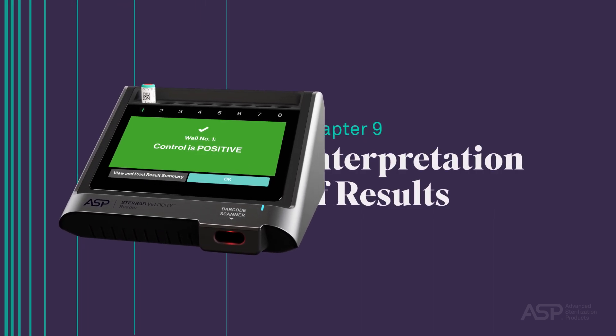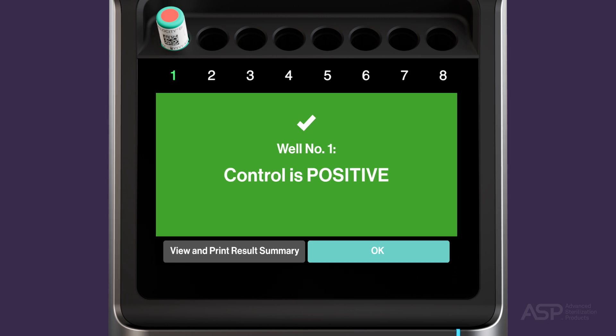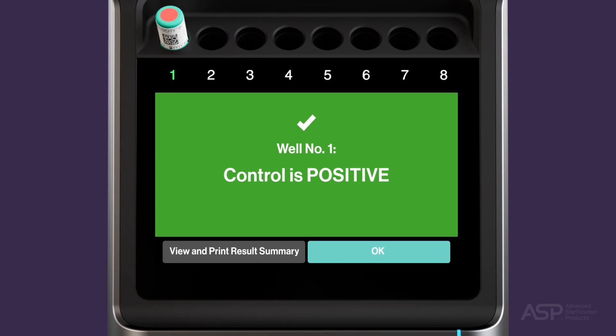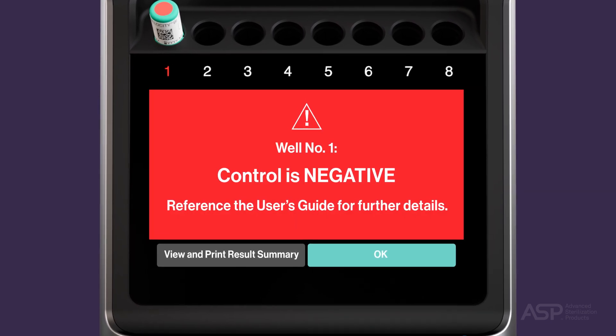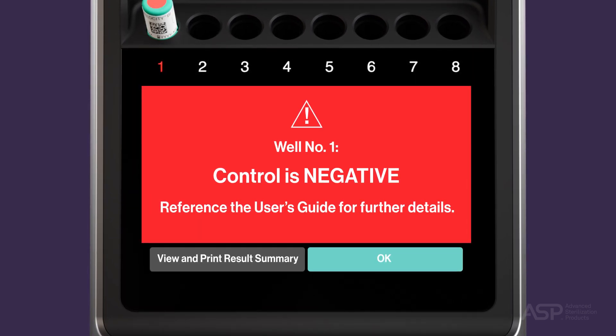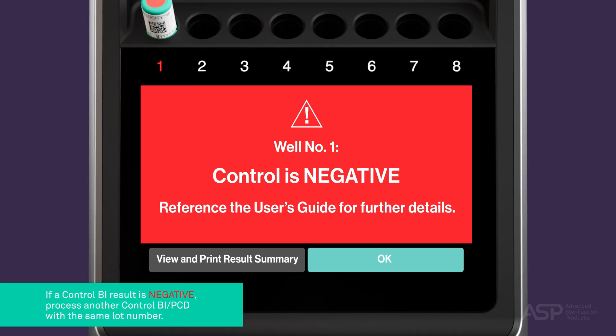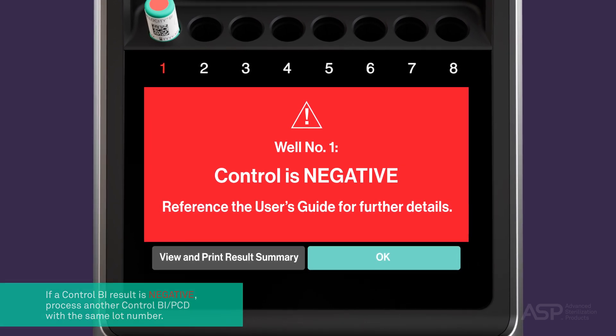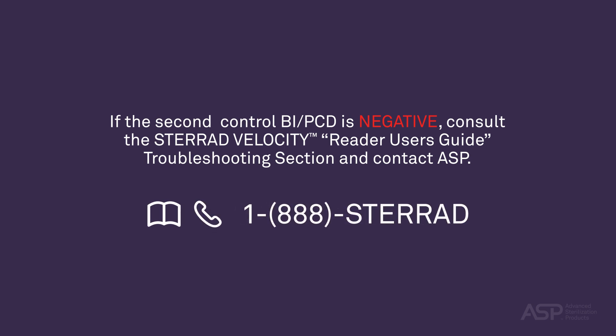Interpretation of Results — Control BI PCD. A positive result on a Control Biological Indicator Process Challenge Device indicates that both the reader and the BI PCD are functioning properly. A negative result on a Control BI PCD could have several causes; refer to the troubleshooting section of the STERRAD Velocity Reader User's Guide for detailed instructions. If a negative result is observed, repeat the test with a second BI PCD from the same lot number. If the second BI PCD is also negative, consult the STERRAD Velocity Reader User's Guide troubleshooting section and contact ASP.